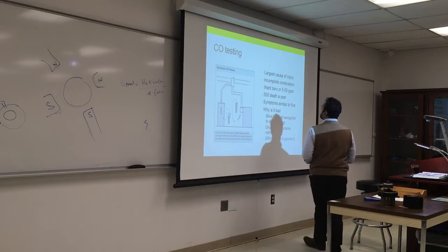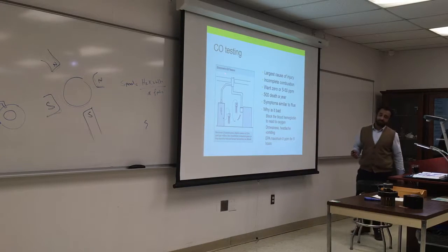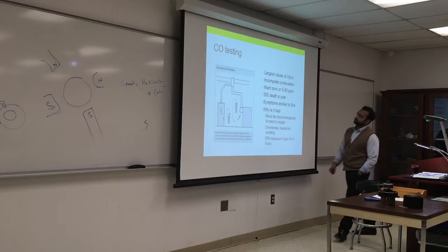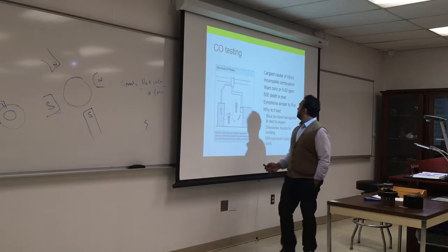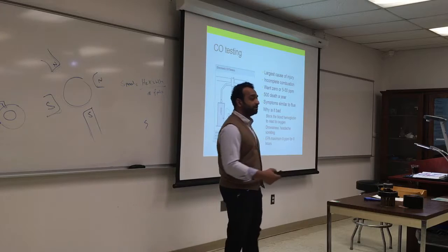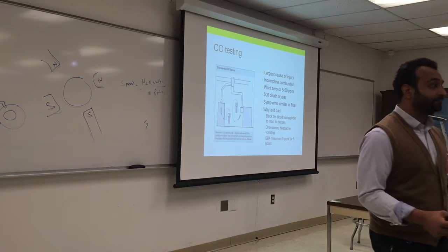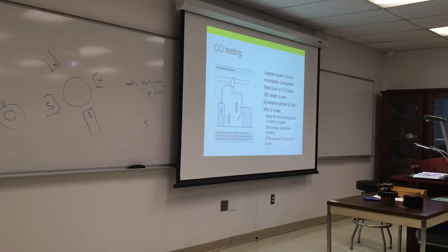CO testing. CO testing, sorry, is the largest cause of injury. It's caused by incomplete combustion. We want to have 0 or 5 to 15 ppm as maximum depending on the situation. In a house that has no combustion, you want 0. It should be 0.